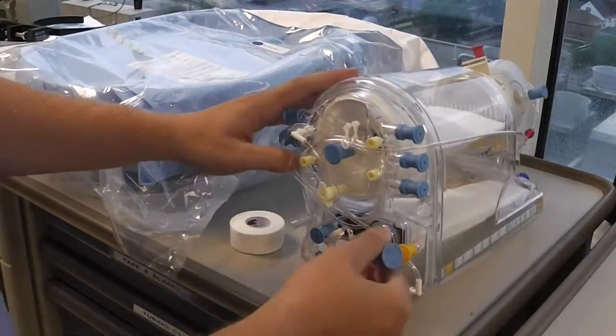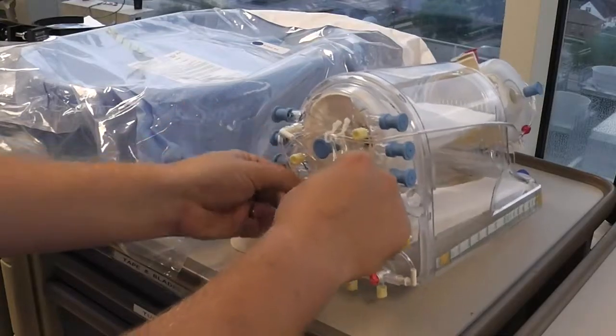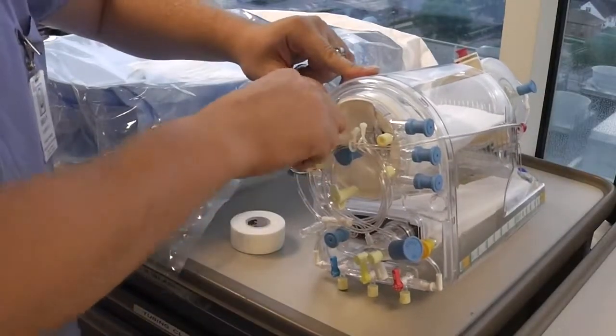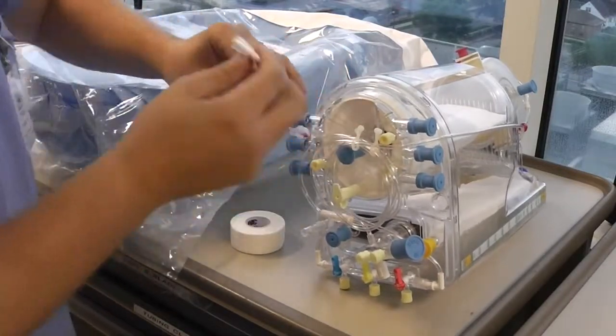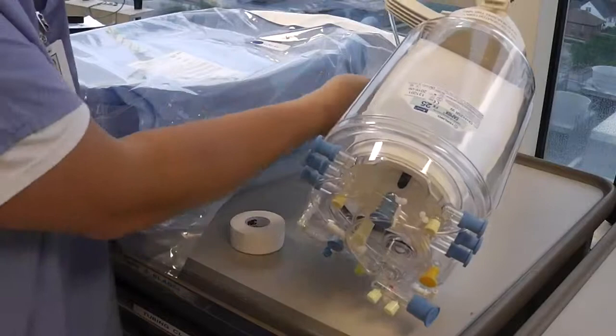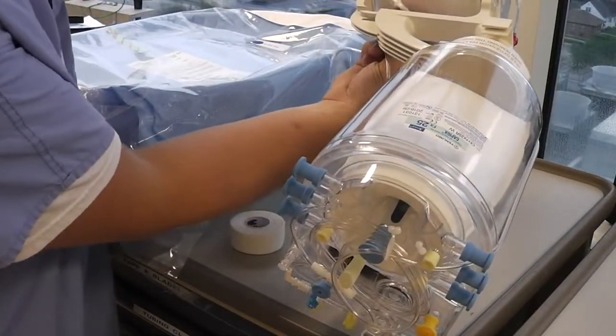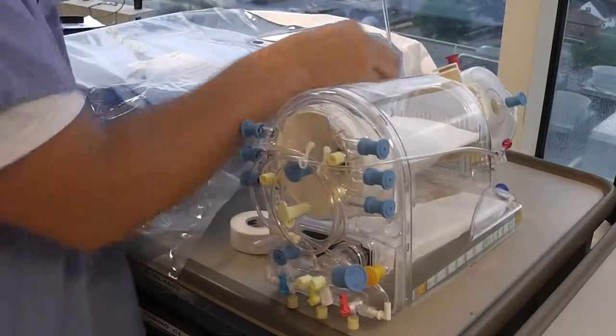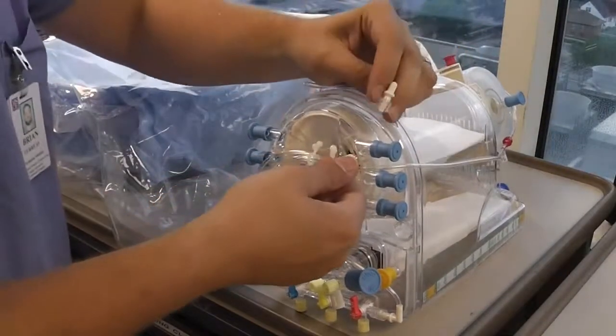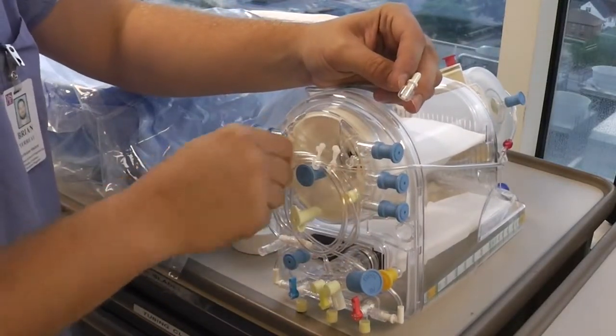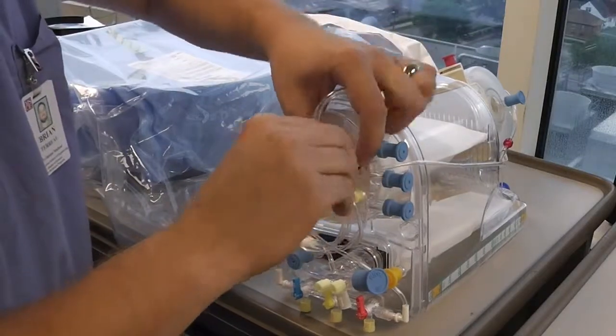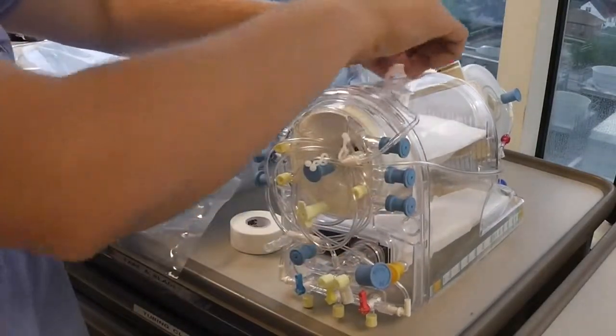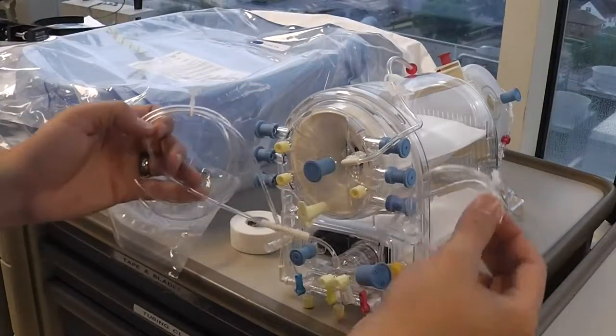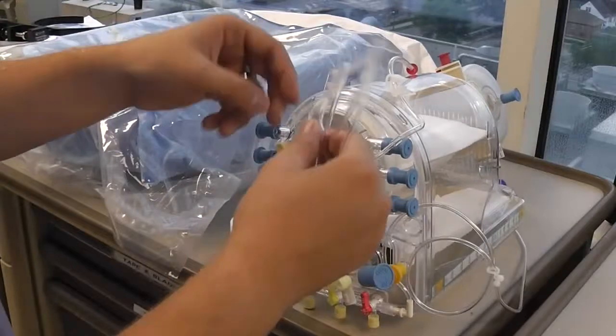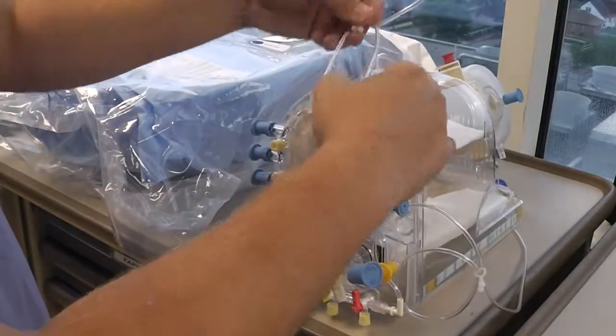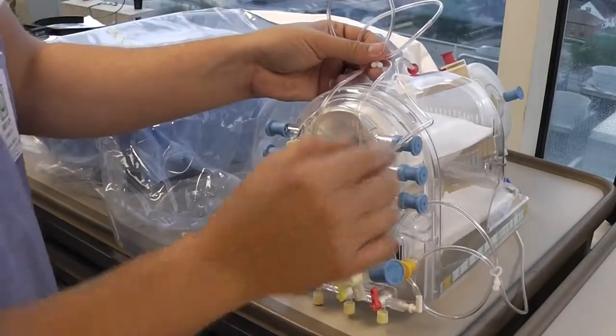I'm going to rotate the venous inlet over here, kind of pull some of these lines out. Remove the oxygenator purge line, and snake it back through this opening here in the oxygenator holder. We're going to come back and we're going to attach this to the right side of the cardiotomy here. We're going to take these lines off the top. This one on the right can just set off to the side. This looped one, we're going to kind of pull these lines out a little bit so that they're laying nicely on top.